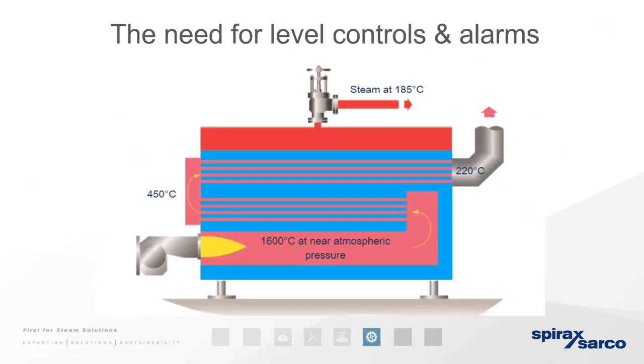So, the need for level controls and alarms. What we're looking at here is a horizontal fire tube boiler. It's called that because it's basically a cylinder full of water lying on its side, with combustion gases running through a series of tubes inside the shell. So here you have the burn tube and your pass tubes.